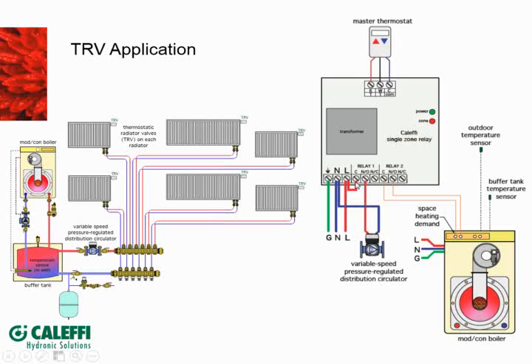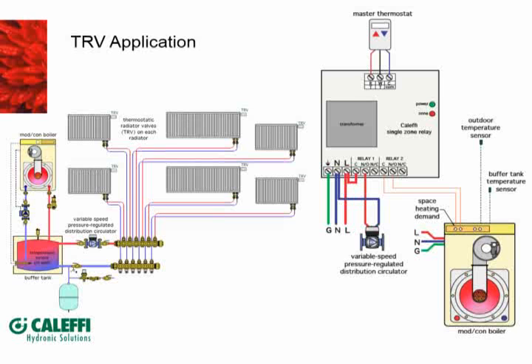What we are doing is giving it this jumper that's factory installed, that does give it the hot leg of 120 over here, so that you can switch 120 here, and this is a dry contact. If you remove that jumper, you basically have 2 sets of dry contacts. So that's a good point. It's a little bit different than the multi-zones, which are dedicated, 24 volt or 120 volt, but this one is more of a dry contact. Yeah, I see the confusion there. The other ones we purposely powered, but this one you've got the option of using as a dry contact or a powered contact by putting a jumper in. Yeah, got it. That's a really good question, good point.